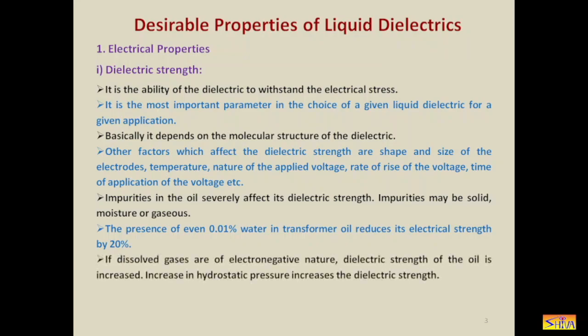If dissolved gases are of electronegative nature, then dielectric strength of the oil is increased. Why? Because electronegative gases remove the electrons from the liquid dielectric. Electronegative gases in general have high dielectric strength. Therefore, they increase the dielectric strength of the oil. Increase in hydrostatic pressure increases the dielectric strength. So in general, when we increase the pressure, obviously the dielectric strength will increase because molecules or atoms are tight, electrons are tightly attached to their respective molecule or atom. So increasing the hydrostatic pressure increases the dielectric strength of the liquid dielectric.